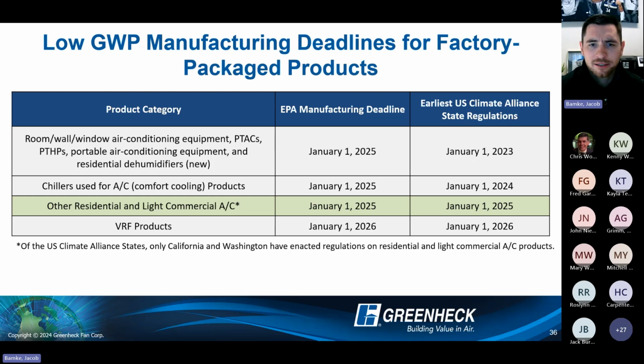There's some deadlines here in this table. So one thing is, obviously when you look at the U.S. Climate Alliance states, there's some adoptions that already started to take place, specifically in those small residential type equipment that you see in the first product category. So the EPA deadline was January 1st, 2025. But California, Washington, for example, January 1st, 2023, they started to leverage the low GWP type refrigerants.